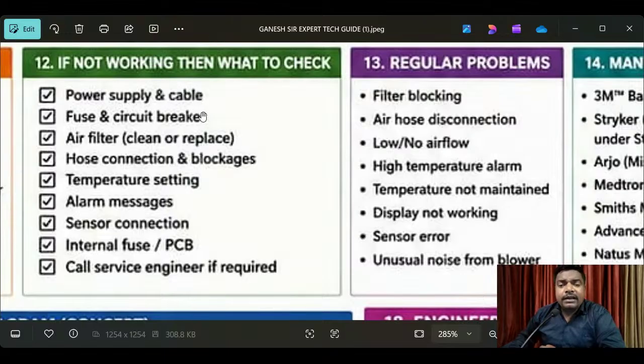If it is not working, check the power supply and cable, fuse and circuit breaker, air filter cleaning or replacement, hose connections and blockages, temperature setting, alarm messages, sensor connections, and internal fuse or PCB, and call a service engineer if required. Okay, so call the service engineer if required. We are the engineers, so why call a service engineer? Yes, if you follow step by step, one by one, definitely you will become a service biomedical engineer. You are the expert.